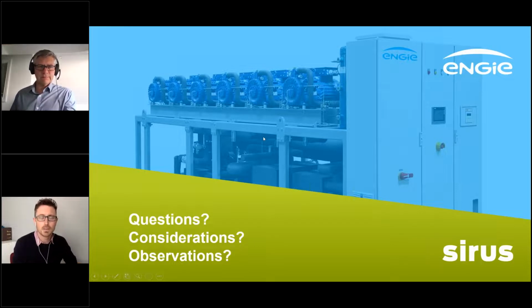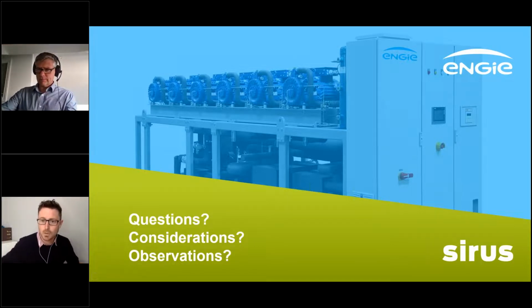Well, thanks so much. That was great. I have a couple of questions I might start things off with. I have a little bit of experience with CO2 heat pumps, and it's a fantastic technology to see incoming water at 10, 11 degrees coming out at plus 70, and with a good COP, it's phenomenal. I suppose the question around that was always the application. The application was always tricky, certainly that I found, that the CO2 heat pump needed that high lift in the temperatures to get that good COP.